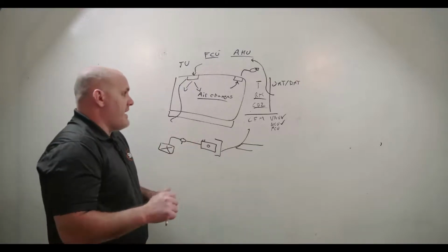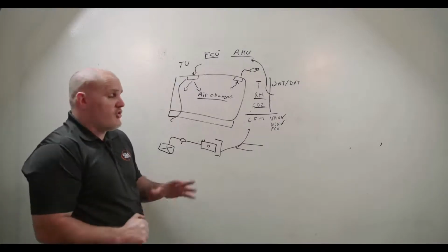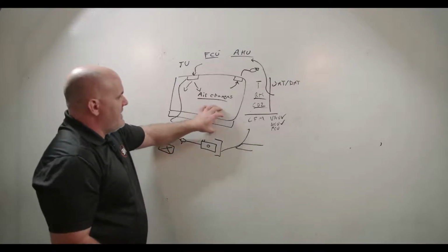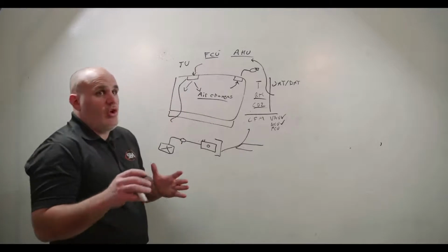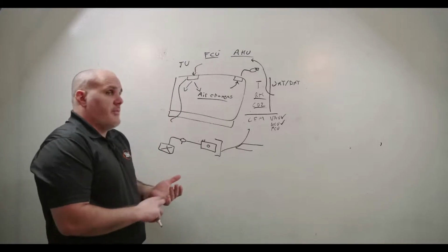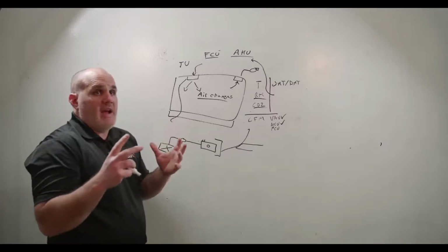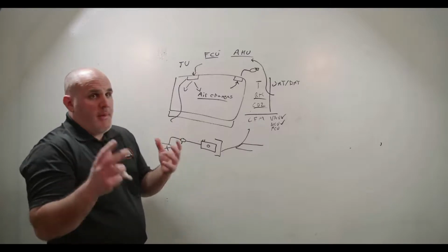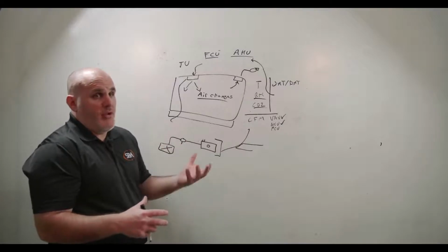So I'm going to hop back over at the screen, see if we got any questions, see what I can answer about space control. If you really understand space control, it's like a linchpin knowledge point for everything else. Space control is going to directly impact pressurization and psychrometrics, and they're going to be interrelated, and those are going to bundle up into air handling unit controls, and that's going to all bundle up into pumping and piping systems as well as hydronic plants, so both boilers and chillers.